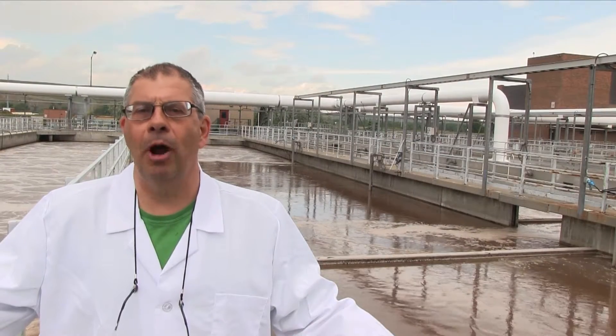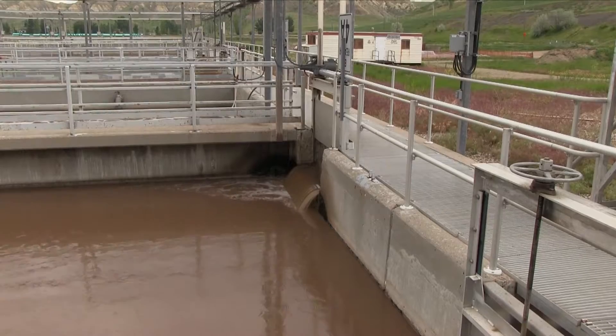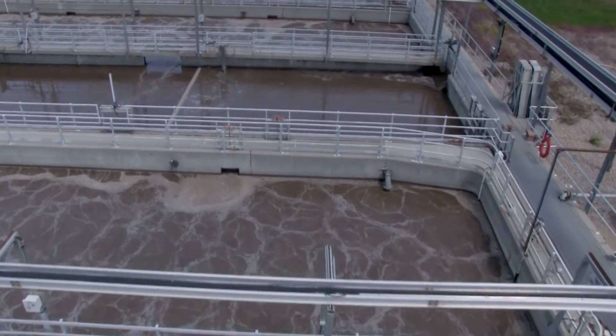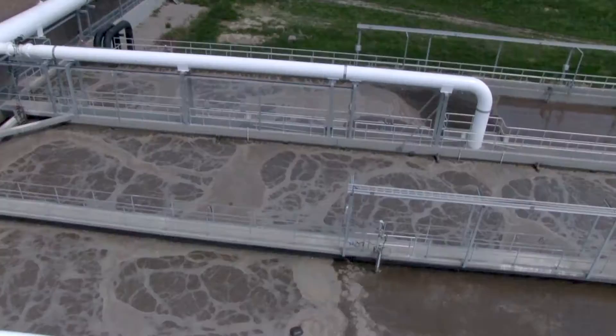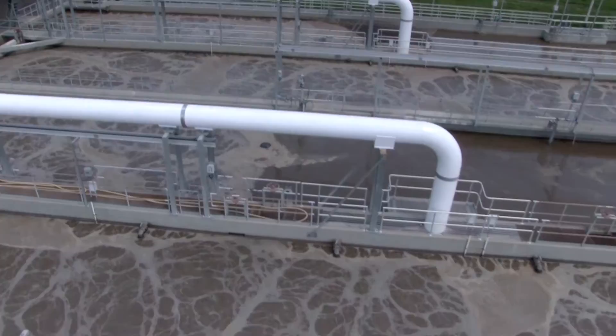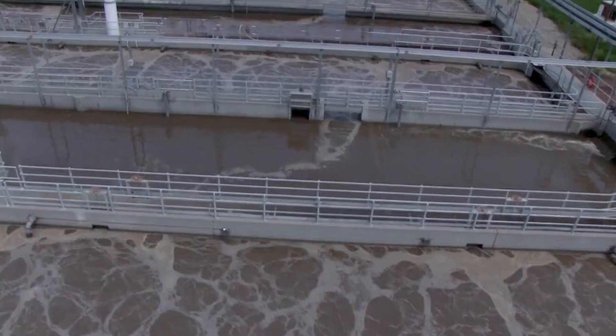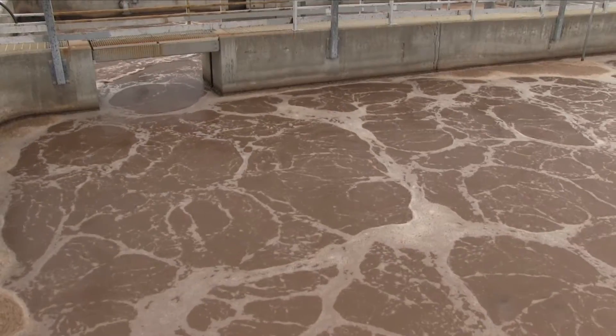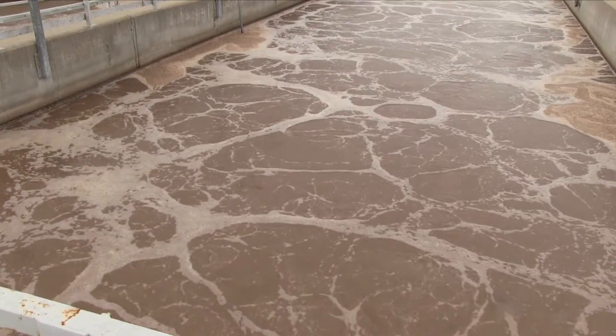The wastewater leaves our primary clarifiers and enters our bioreactors. The bioreactors are where we keep the bacteria on the plant. The bacteria's job is to use all the fine dissolved solids in the primary effluent and use it as a food base. It goes through our five bioreactors, passing through a variety of zones: the anaerobic zone, then two anoxic zones, and then an aeration zone. Through these different zones, fine particulate matter is removed as well as the nutrients dissolved in the wastewater.